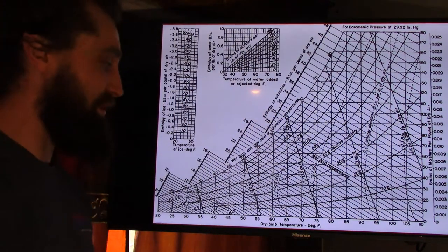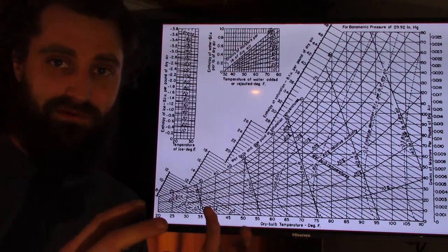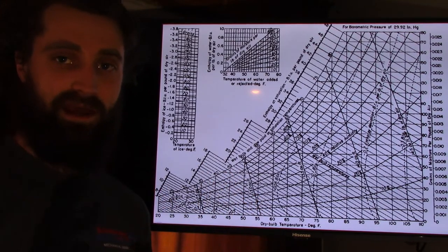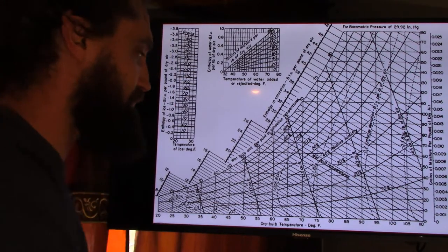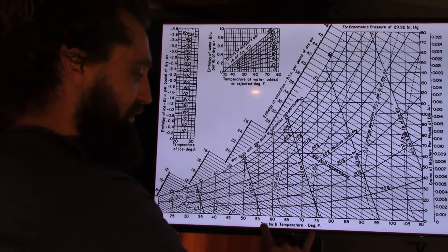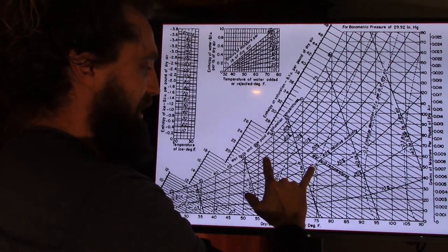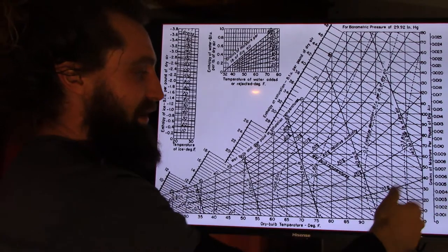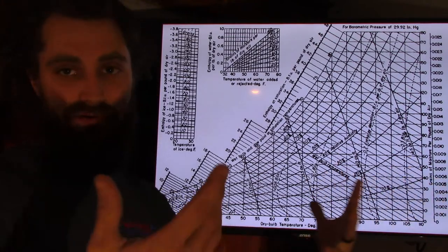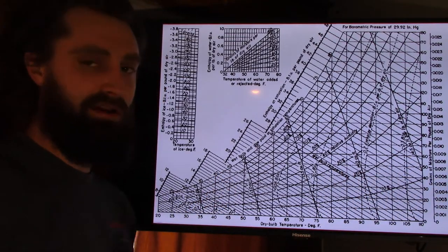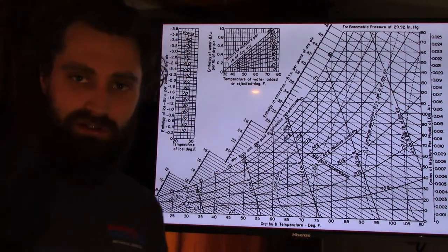We know that we are below the dew point of our evaporator, or of the air. The evaporator is actually removing moisture. We got to take that into account. There's a tremendous amount of heat energy wrapped up in all of that moisture that we are sending out the condensate drain. So what we would then do is we would go to where these guys meet, we'd go across to our grains of moisture per pound. Like I said, I think we were at like 45 on the supply and about 52-ish on the return. I'm going to use those numbers just because they're easy to work with, and I don't have like a straight edge here. But let's just see what those numbers do for us.